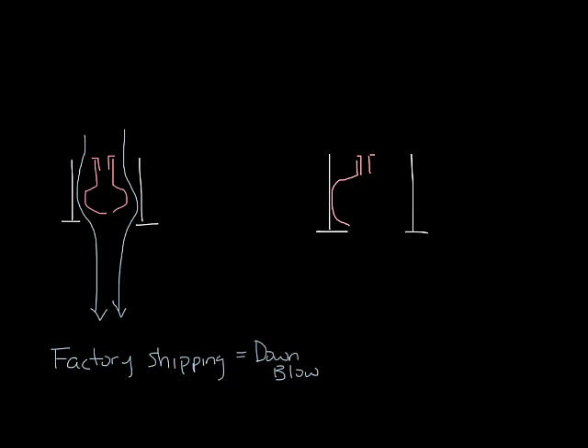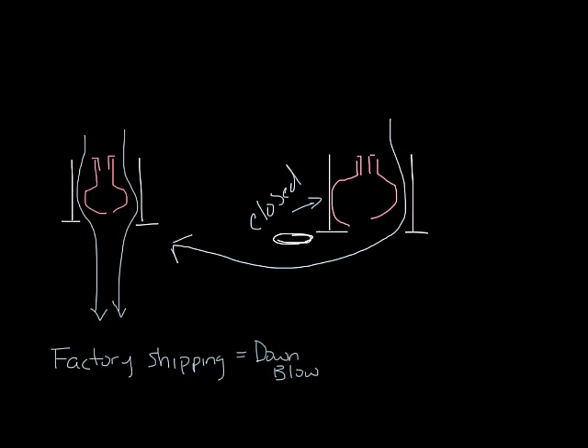So now if you look at the pattern controllers you kind of want something like this where one is all the way up against the side and the other one is pulled down to the center. What happens here is you're dampering one side, it's completely closed so the air can't get by and as the air comes out you've got this low pressure zone right here next to the ceiling and the air is going to come out and hold onto the ceiling and blow in this case to the left.